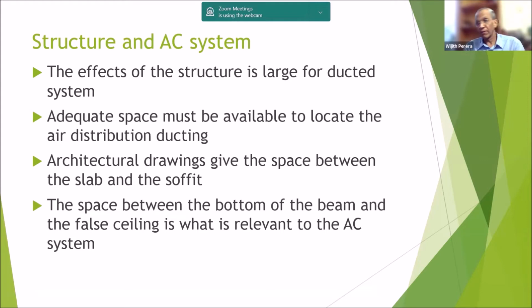There are beams running in both directions, longitudinal and lateral. Then the ducts can't go against the soffit, drop down, wrap around the beams and go up again. No, it can't be done. A pipe may be possible to do. Ducts will have to run straight.